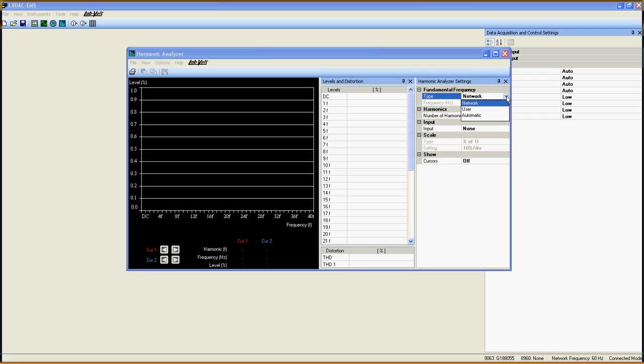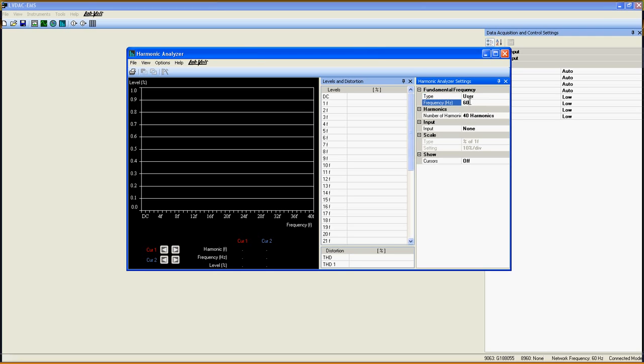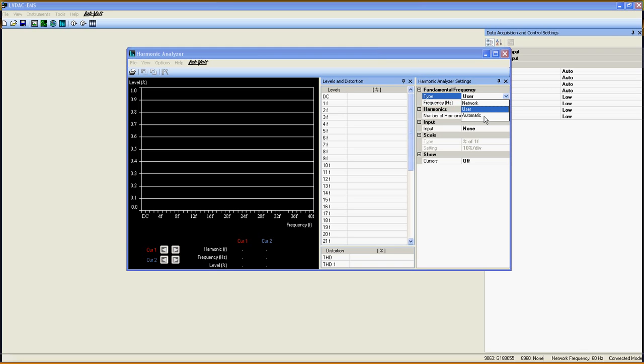You can choose between network, user, or automatic. The first one will use the frequency selected when you open LV DAC. User will let you select the fundamental frequency as you want and automatic will let the Harmonic Analyzer find the fundamental frequency for you.